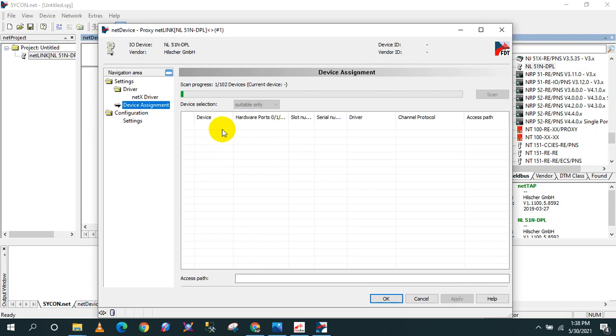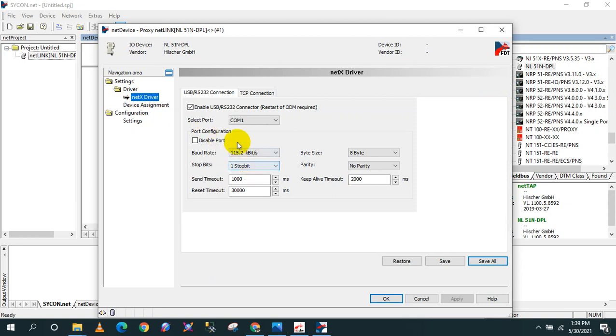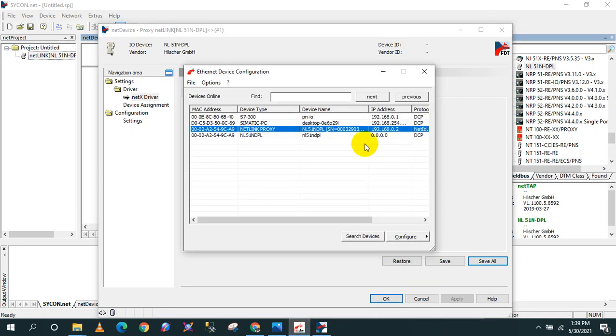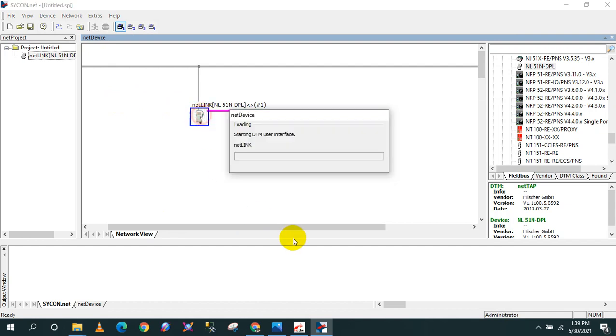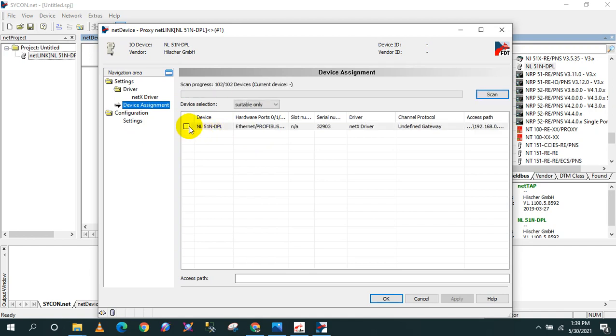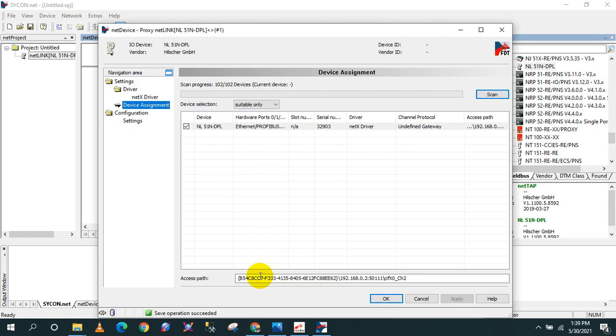Then it's going to search the available module. In default, you cannot see that one. So all you have to do is click the netX driver, then enable the TCP, and then the IP address. This is the IP address that we configured a while ago. Then click OK. Again, I will click. You will search and then it should appear here, your Hilscher. Tick the box and then click apply. So now it is connected to your Sycon.net. Then click OK.